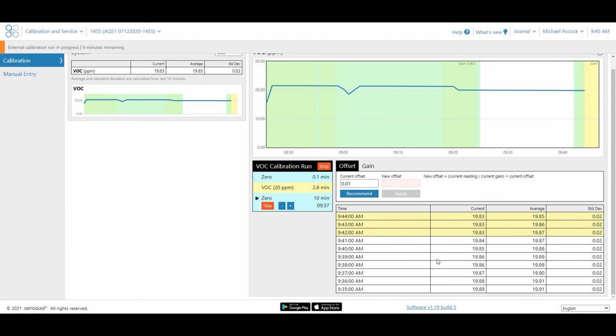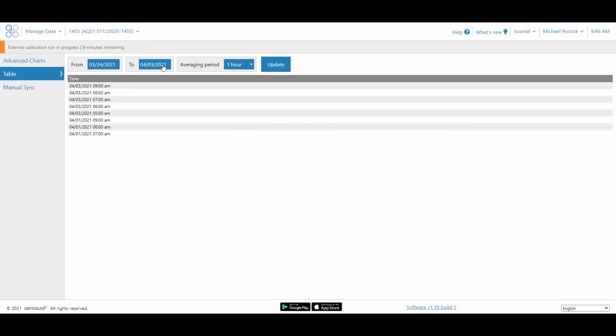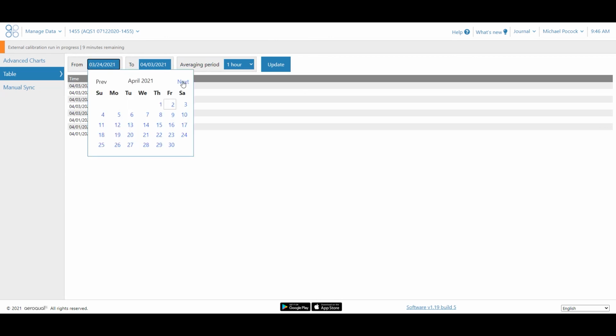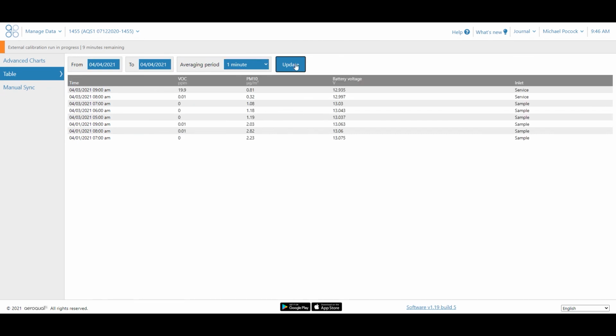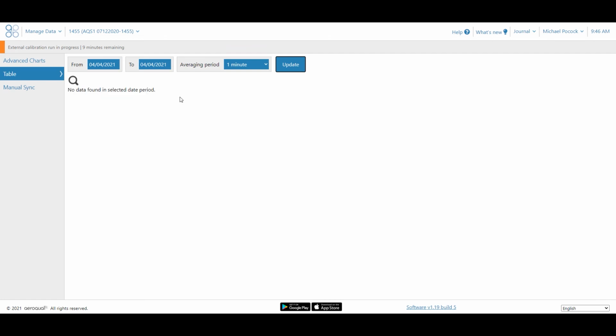If you were just doing a quick calibration check, you don't even have to go in this area. Just put on your gas cylinder, and then have a look at your readings in your manage data section. Once you've applied that gas, wait 2 or 3 minutes for it to change. It's going to take that time, as I said, because it's pulling at a very low flow rate. If you were looking at your last minute data, you could just look at your data here and satisfy yourself that you were reading at around your span.